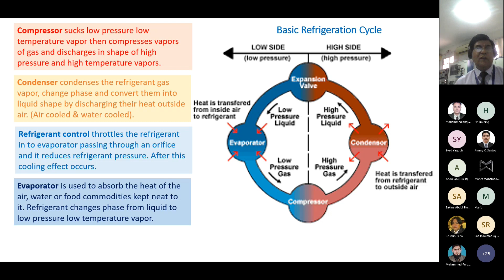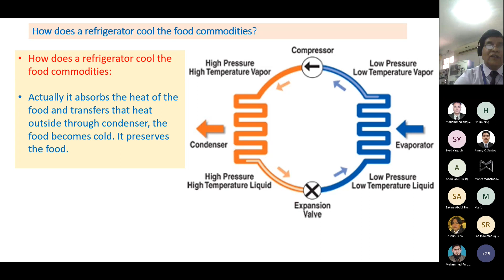Refrigerant changes phase from liquid to low pressure, low temperature vapor. In the condenser it was from vapor to liquid, a phase change, and now in the evaporator from liquid to low pressure, low temperature vapor, the phase is changed. So this is another cycle of a different shape, but it is the same cycle. This mechanical refrigeration cycle is the same, only the additional part is the dryer.